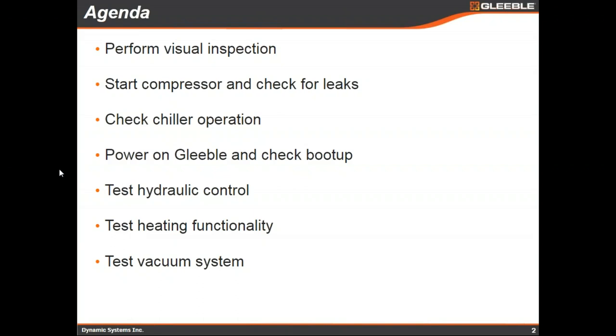The Gleeble is a fairly complex system with a lot of components that, if they have been shut down, need to be turned back on and verified to function as they did before. The first agenda item will be a quick visual inspection, mostly looking for leaks or other issues that may have been developing over time, which might indicate where leaks will come from once we turn it back on.